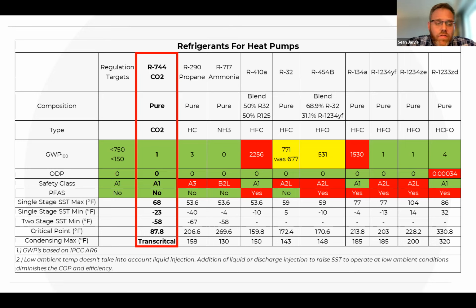The current classification of R32's GWP is 677. But as of 2 months ago, the IPCC regulations AR6, the 6th edition, pushed it up to 771, which unfortunately is over that threshold. I'm sure there's going to be a lot of pushback on that recalibration, but it puts it in hazardous territory on regulations that may or may not allow it to be used.